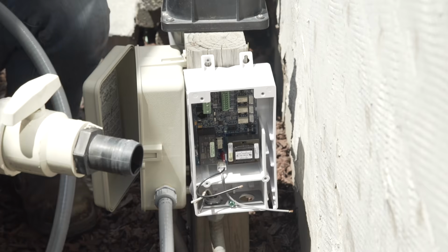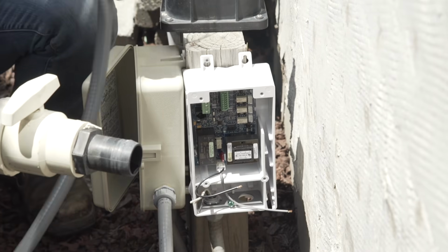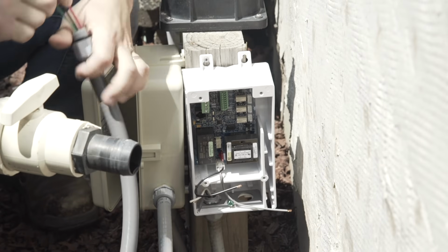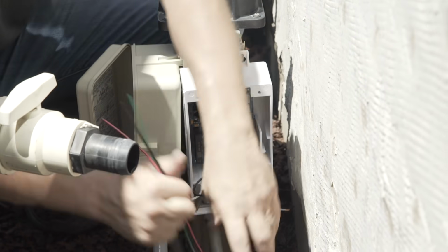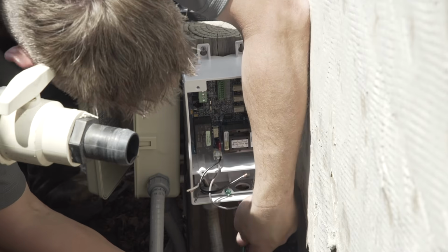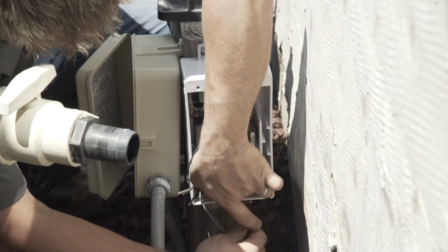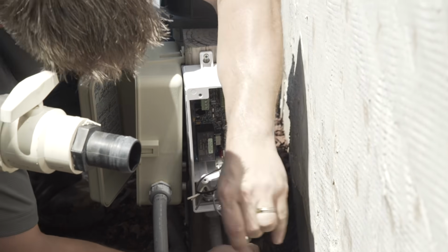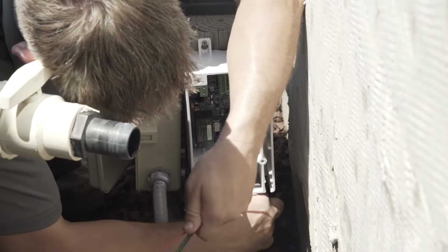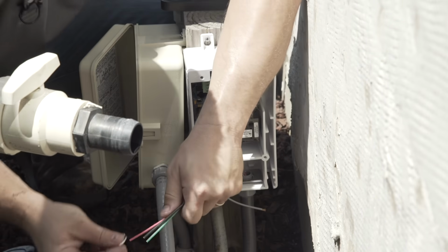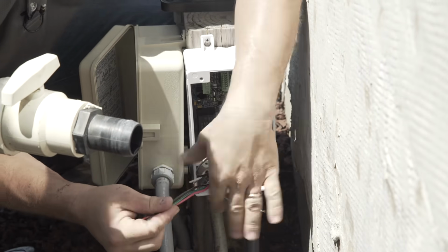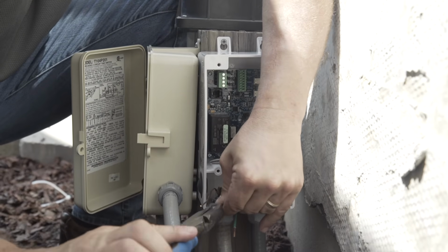Step 2. Wiring the high voltage from the wiring hub to the VS Omni pump. Once the VS Omni pump is installed and plumbed, run the supplied 6-foot conduit from the hub to the pump. There are 2 6-foot conduits included. The second can be used for the smart relay connection. Now connect the high voltage wiring inside the wiring hub.